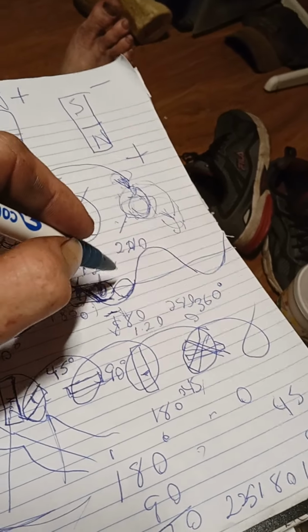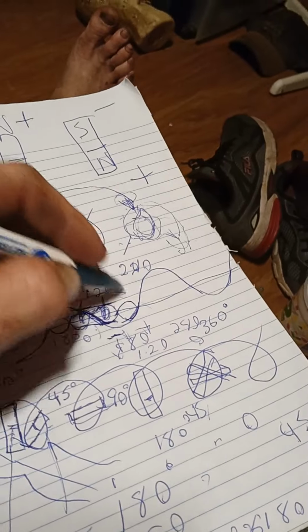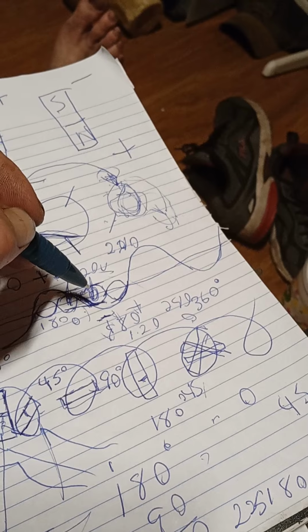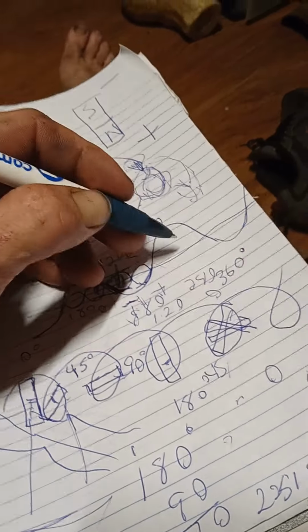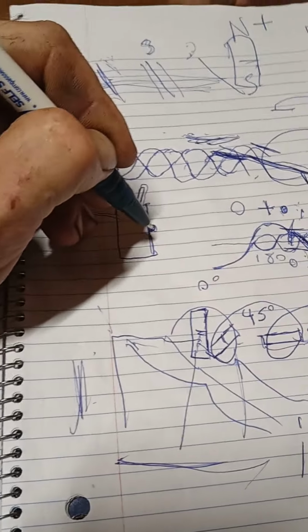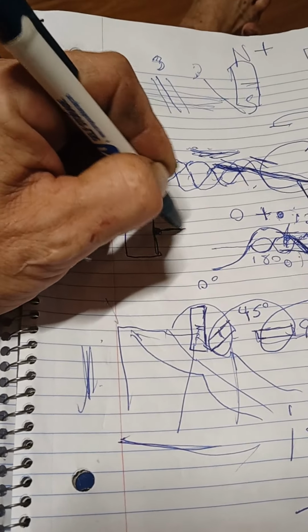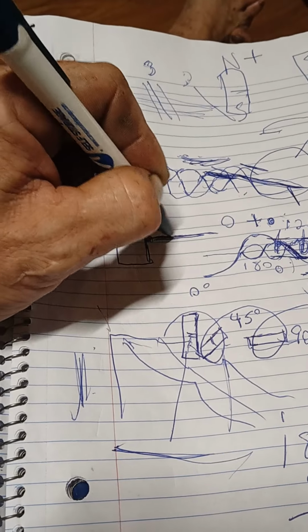And when it reverses, the positive from one side and the negative from the other side, and split it in half, and you get 120 volts on either side. But if you wanted to pull the whole thing, that's where you get the whole 240. The way this works at the transformer is it has what they call a center tap, right? And this is the neutral line, the white wire that comes in, and it's also ground. Either one works.